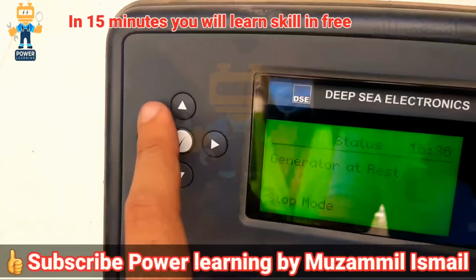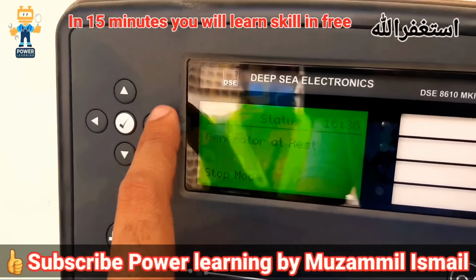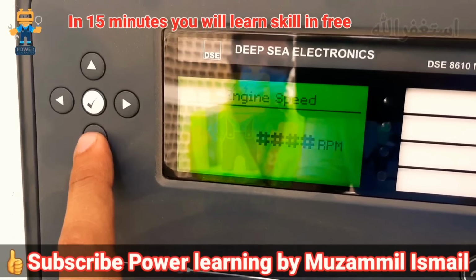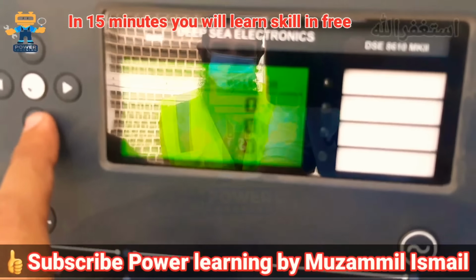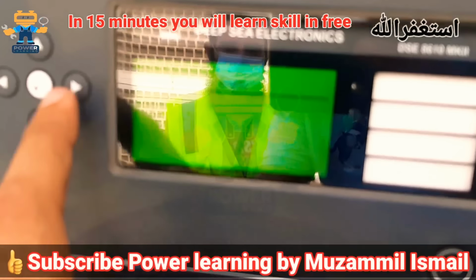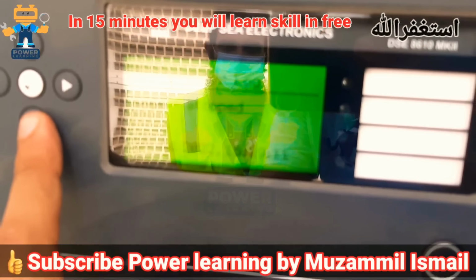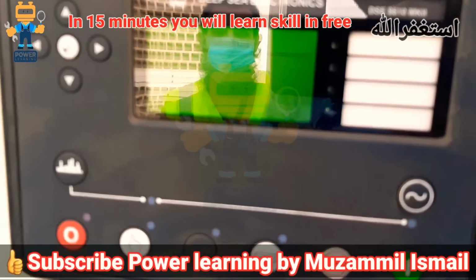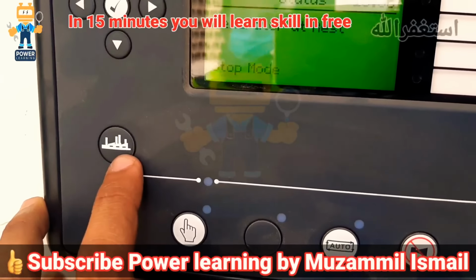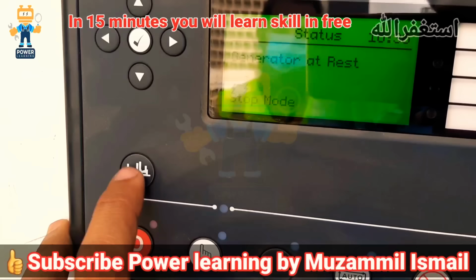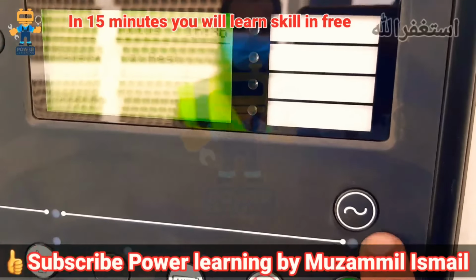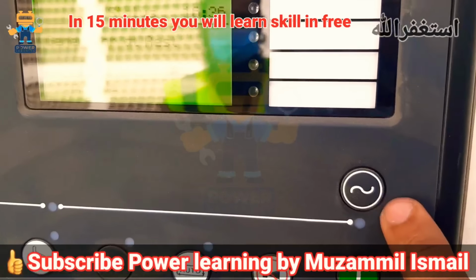Okay, these 4 buttons are for navigation, to check the engine parameters like this. Okay, you can check all the parameters. After that you can check the generator parameters, bus parameters, alarms, ECU current, event logs, you can check all the event logs. Okay, so in this way, it is a very easy and very simple controller. This button we are using for manually turning off the breaker, and this button for manually turning on the breaker. These two are the on and off commands for the breakers.